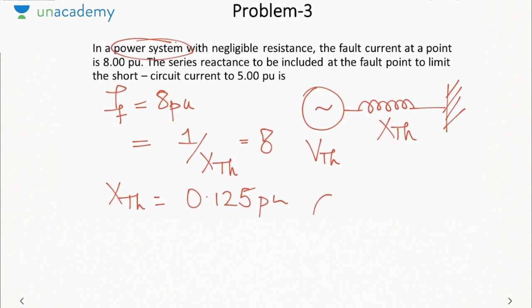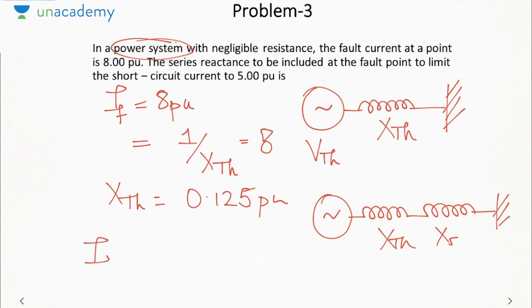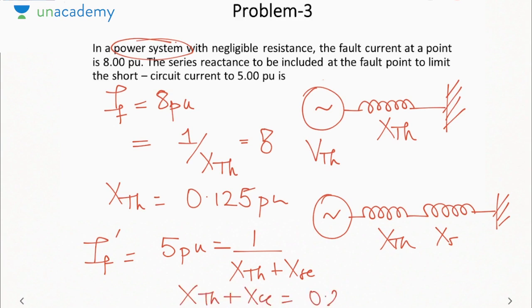Now we are considering a series reactance. So the system will look something like this: X Thevenin, X series. So the fault current must be 5 pu, which will be equal to 1 upon X Thevenin plus X series. So here X Thevenin plus X series will come out to be 0.2 pu, which implies X series will be 0.075 pu. Okay, this much reactance must be included in series to limit the fault current to 5 per unit.